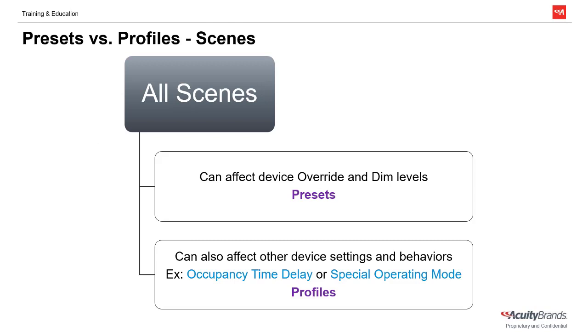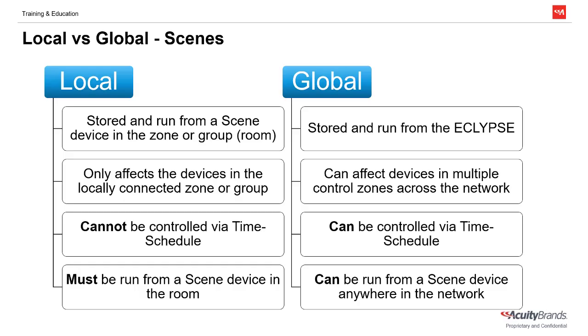In nLight, all scenes are broken down into two types. One type only affects lights' on, off, and dim levels — these are called preset scenes. The other type of scene can affect other device behaviors by changing their current settings. For example, changing an occupancy sensor's time delay, or a light fixture's special operating mode. Both types of these scenes can either be local or global.